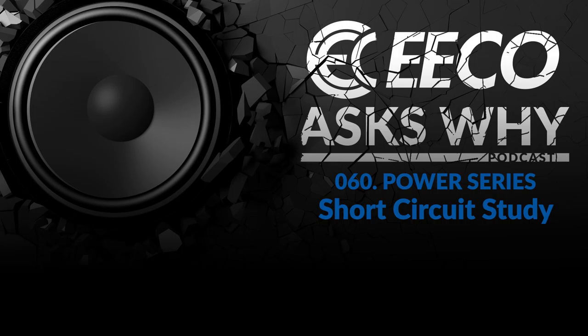The other answer is that it depends on how much of an upgrade you're doing and how frequently you're upgrading your system. If you're putting in a lot of motors greater than 50 horsepower, motors that could contribute back into the system, then maybe 5 years is too long. Maybe every year or two. It just depends on how frequently major equipment is being added to the system.